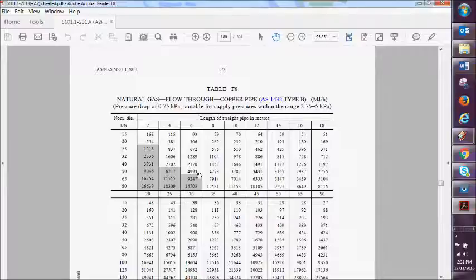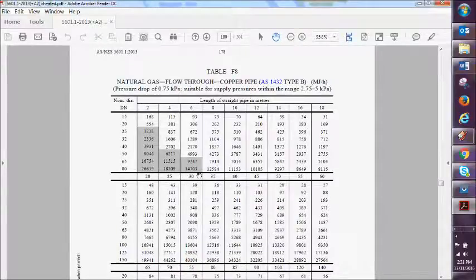It depends on the meter and the area. There are areas in Sale where it's only 1.1 kPa. You might come across a house, and in some areas it's 1.1, in some it's 2.75. I've heard of blokes coming unstuck. Can you up that kPa? No, it is what it is. You shouldn't be mucking around with the gas meter at any stage.